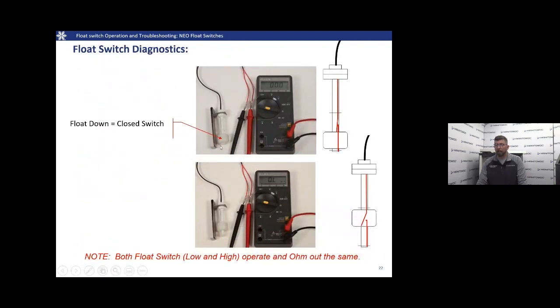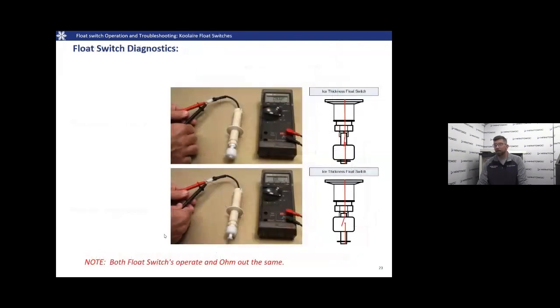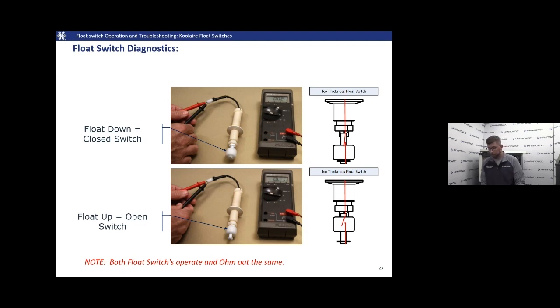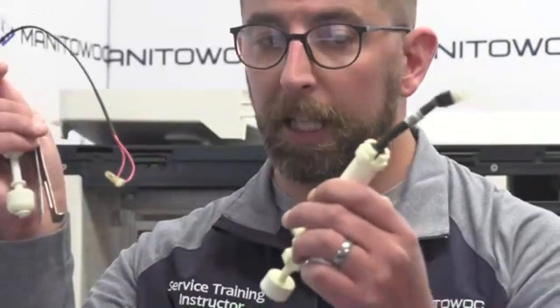On screen you can see a float in the down position being ohmed out, and below that in the up position, again being ohmed out, seeing what we're expecting to see. Another picture shows a Koolaire float — you'll notice that this one has a plug on it, unlike the NEO with wires coming out. So you can see the differences between our floats: the NEO with the wires and the Koolaire unit with just a plug.